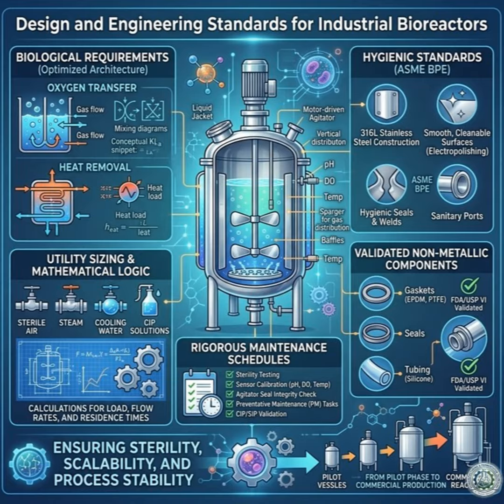You absolutely cannot. The choice of elastomer has to be specifically mapped to the chemistry of your process and your cleaning cycle. Because if your automated cleaning process uses a harsh solvent or an acid that slowly degrades standard silicone, then over the course of 50 cleaning cycles, that silicone gasket is going to start breaking down. It will shed microscopic chemical particles, which are known in the industry as extractables and leachables, directly into your medicine or food product. Yikes. Or worse, the seal loses its integrity entirely, microscopic gaps form, and a wild contaminant gets sucked into the tank. Which transitions us to a harsh, unavoidable reality of manufacturing. A pristine, perfectly polished stainless steel vessel with brand new Teflon seals is only a snapshot in time. It looks magnificent on day 1. But what happens on day 100? What happens on day 500?